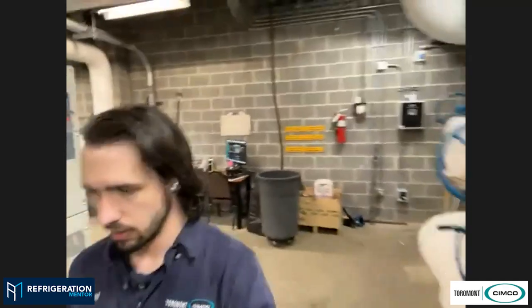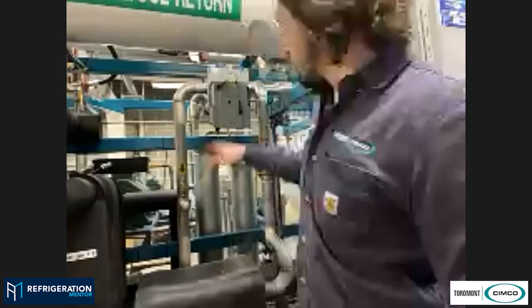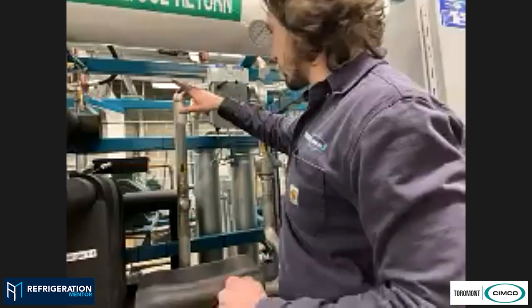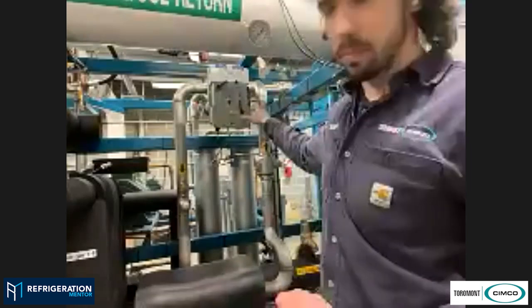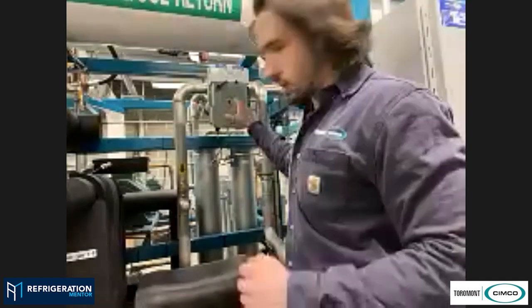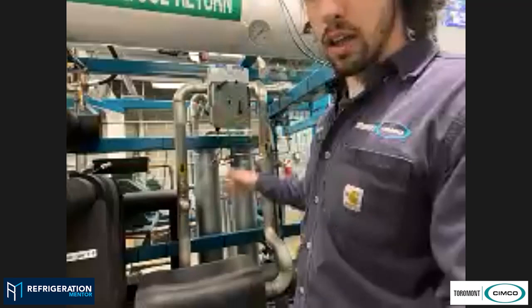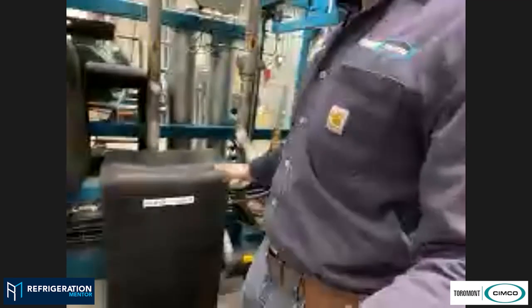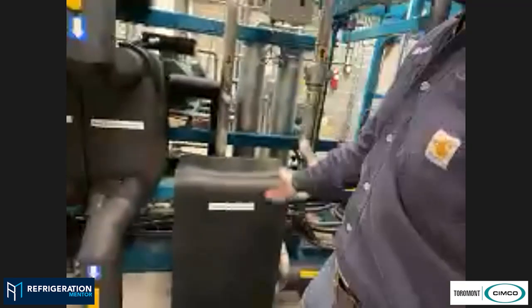I wanted to bring that up before we go to the backside of the package and show off the heat exchanger, because that's the next step. This is our motorized ball valve for heat recovery. If we're not calling for any heat recovery, the discharge gas goes directly up to our gas cooler. In the event we are reclaiming heat, which is very common, we have a brazed plate heat exchanger here that the flow is diverted to, and then we go up to our gas cooler.